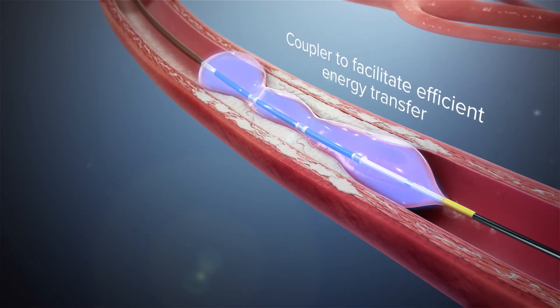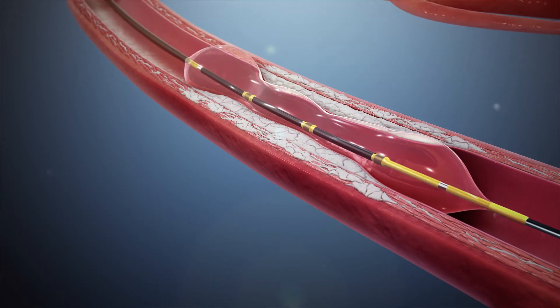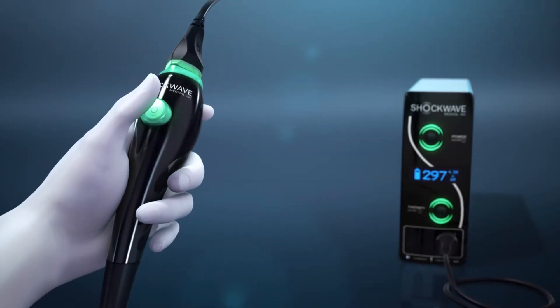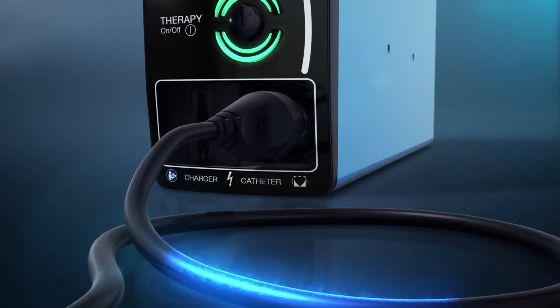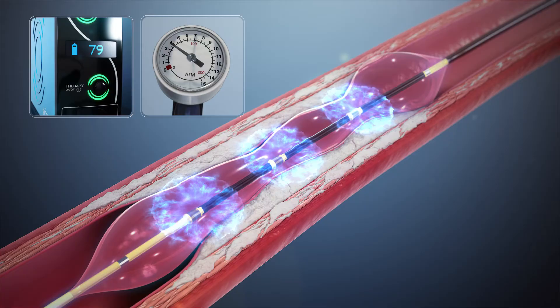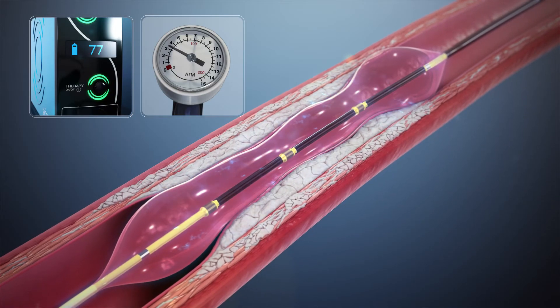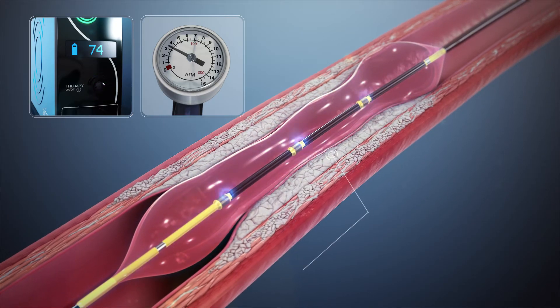The fluid within the fully apposed balloon acts as a coupler to facilitate efficient energy transfer of the sonic pressure waves into the vessel wall to reach the calcium. The generator produces three kilovolts of energy that travels through the connector cable and catheter to the lithotripsy emitters once per second.